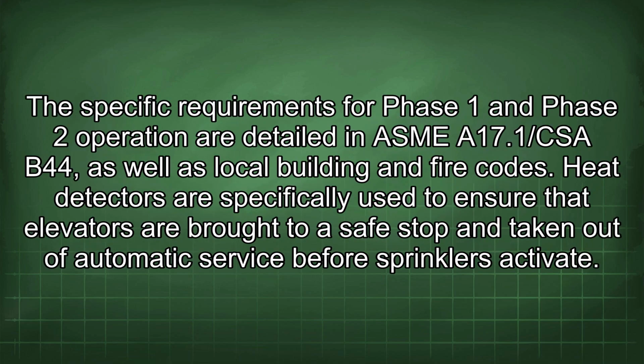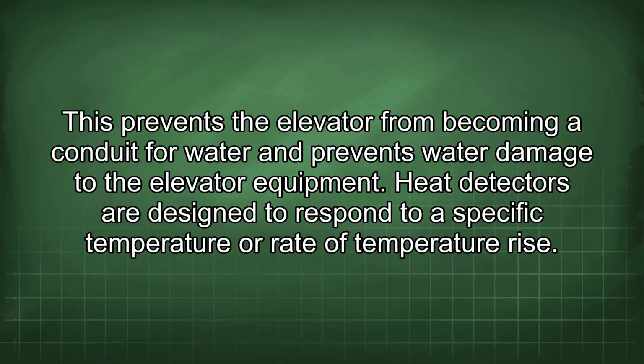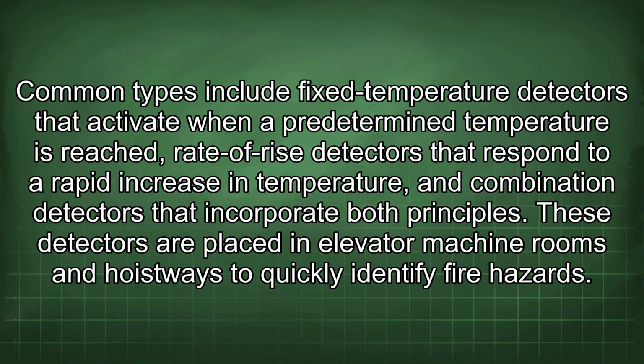The specific requirements for Phase 1 and Phase 2 operation are detailed in ASME A17.1/CSA B44, as well as local building and fire codes. Heat detectors are specifically used to ensure that elevators are brought to a safe stop and taken out of automatic service before sprinklers activate. This prevents the elevator from becoming a conduit for water and prevents water damage to the elevator equipment. Heat detectors are designed to respond to a specific temperature or rate of temperature rise. Common types include fixed temperature detectors that activate when a predetermined temperature is reached, rate of rise detectors that respond to a rapid increase in temperature, and combination detectors that incorporate both principles.